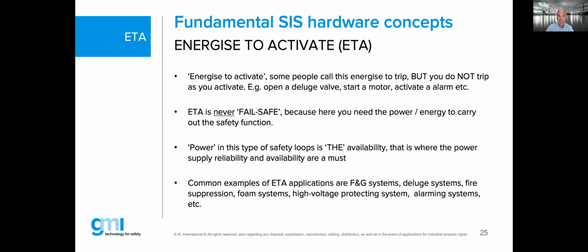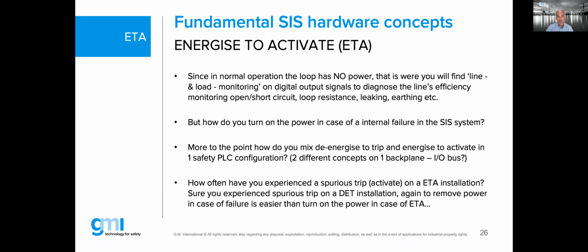Those type of interlocks are never called fail-safe because we need that power to do something. That means that power, referring to the power supply role in your safety function, becomes a very, very, very big availability issue now, in the same story as it was a small availability issue also in the de-energized to trip. So power supply is indeed the availability issue. And common examples will be fire and gas, deluge, fire suppression, foam systems, high voltage protection, alarming, etc., etc.